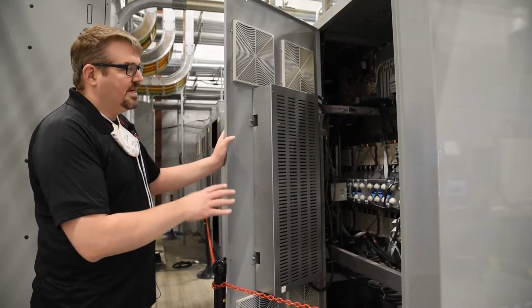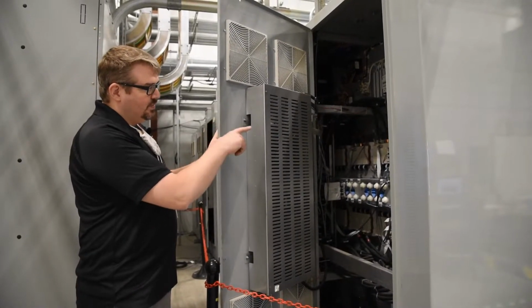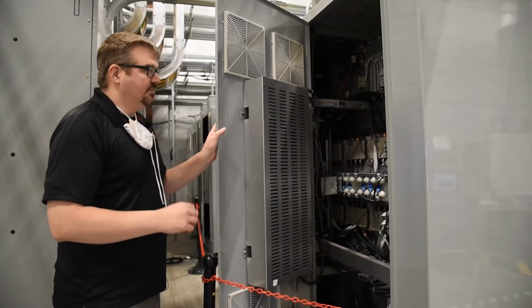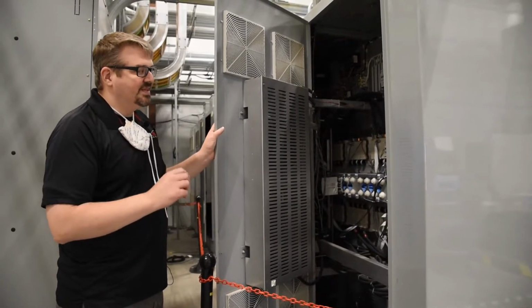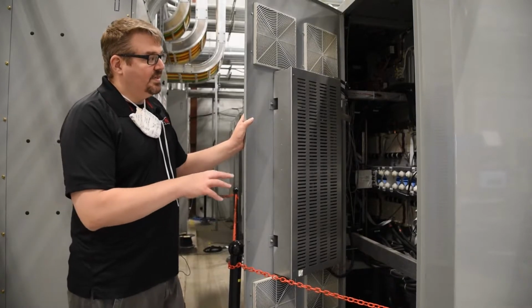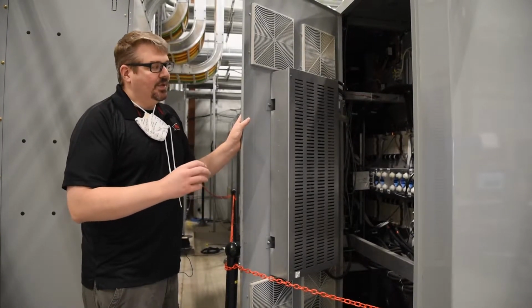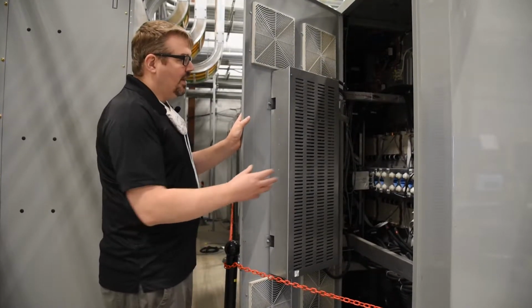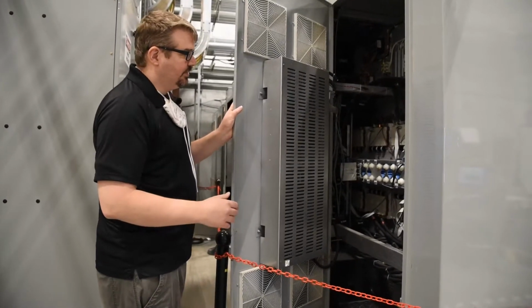This is a standard back-to-back converter, custom built. Each one of these switching positions that you can see, the white rectangle, is rated for 2,000 amps. So in each switching position we have 3 of those, so 6,000 amps rated for each switching position. With these we can do grid simulation, vary voltages and frequencies, but we can also do the regenerative testing we discussed earlier.